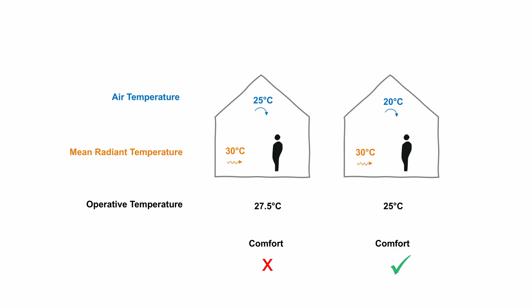So that was a lot of theory about thermal comfort. Let's have a look at the mean radiant temperature in this space. Here I have an instrument which helps us measure the mean radiant temperature in the space, the temperature of the ceiling, the floor, and the four surrounding surfaces.